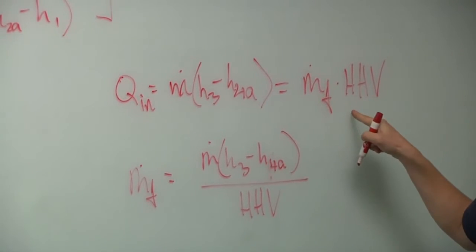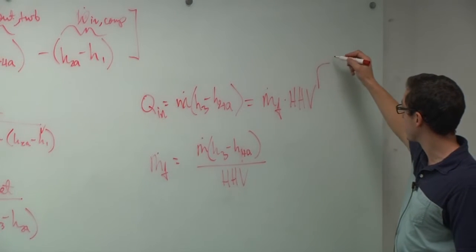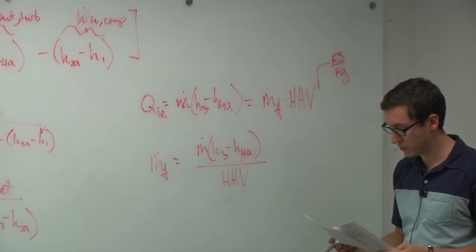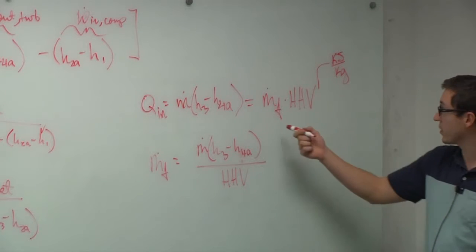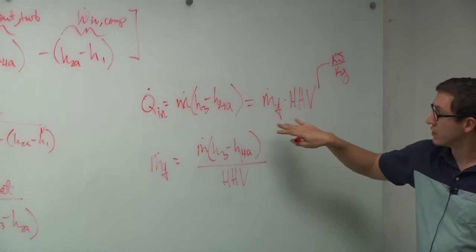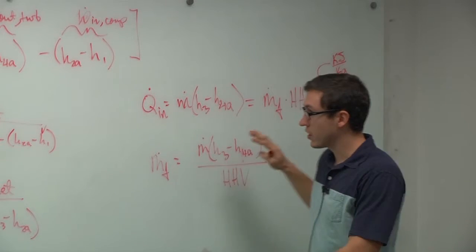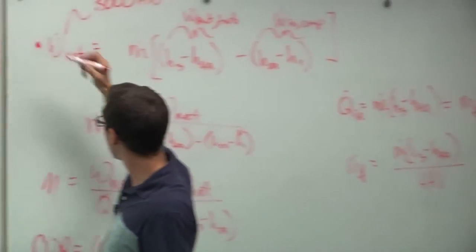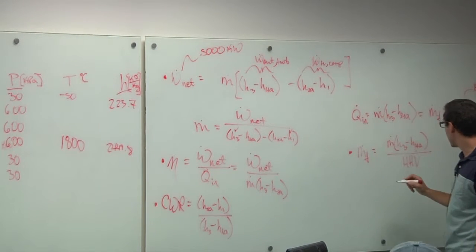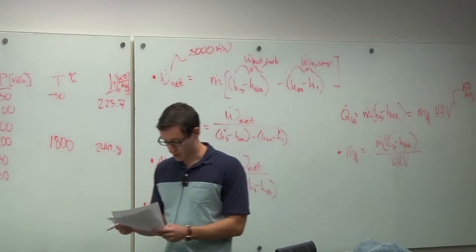That last thing we need is the fuel rate. We can say that Qin is equal to m dot times H3 minus H2A, which is also equal to... This m dot is the air. We say the m dot of the fuel times the heating value of the fuel. We can find m dot fuel by dividing this energy transferred to the air by the heating value. Have y'all ever seen this heating value equation before? So, what we're saying here is that this is in kilojoules per kilogram. They have that listed on your handout. Where it says heating value is 42,500 kilojoules per kilogram. If we multiply that by the flow rate, we get our Q dot in. This is basically at what rate is the fuel providing heat to this air, which is moving this fast and changing in energy this much.